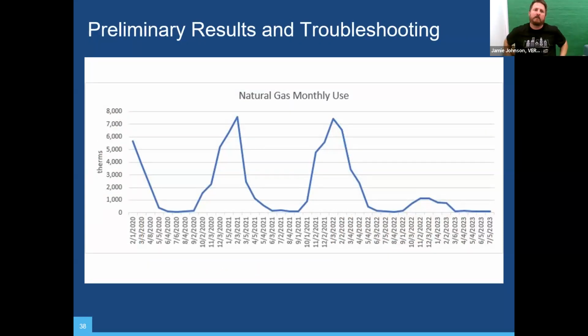You can see natural gas hasn't gone to zero. We did have one rooftop unit left running for the rotunda through the winter, so that small spike, about 1,000 therms, is a portion of that. They also have a commercial kitchen and several hot water heaters which we have not electrified yet. But you can see the reduction. 7,000 therms at $1.30, or whatever we were at in December, is $9,000 to $10,000 a month—it would range, because December was a pretty cold month in Chicago. But this is significant. You cannot decarbonize heating without removing natural gas from the picture, and we did that in this building.